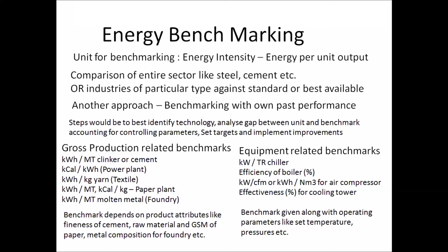Now, talking of individual equipment benchmarks: for a chiller, kilowatt per TR; for a boiler, percentage efficiency or steam to fuel ratio; for a compressor, kilowatt per CFM. All these are benchmarks for individual equipment. So plant level is one benchmark, and individual loads or utilities is another benchmark. Both help us see whether our energy performance is okay or not.